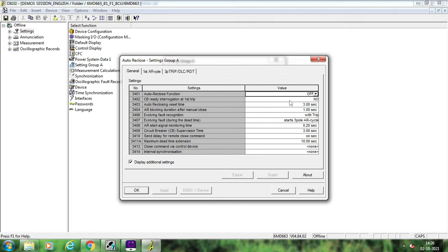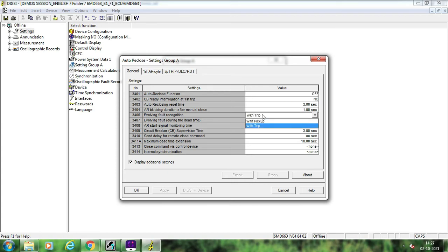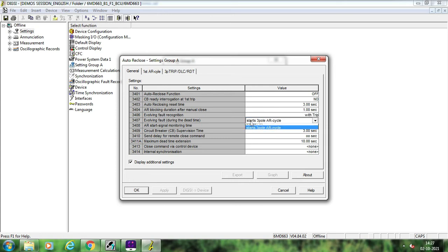You can set the CB ready interrogation as yes or no depending upon your requirement and scheme. Now the important thing is evolving fault and the decision that the BCU should take during an evolving fault. An evolving fault means suppose there is a transient R-phase to ground fault and within the dead time of one second this fault changes from R-phase to ground to R-Y to ground or Y-phase to ground. These types of faults where the fault changes from one type to another are known as evolving faults. In case of an evolving fault you can decide whether your relay detects it from trip or from pickup, and what action to take — whether to start a three-pole auto-reclosure cycle or block the auto-reclosure cycle. Generally in transmission systems we block auto-reclosure.